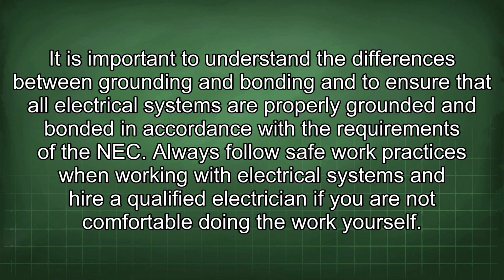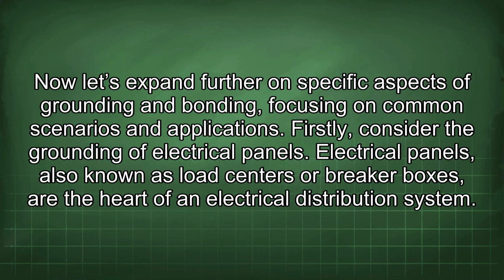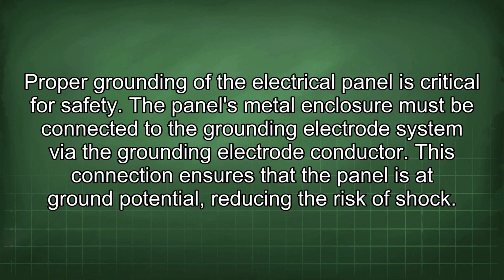Now let's expand further on specific aspects of grounding and bonding, focusing on common scenarios and applications. Firstly, consider the grounding of electrical panels. Electrical panels, also known as load centers or breaker boxes, are the heart of an electrical distribution system. Proper grounding of the electrical panel is critical for safety. The panel's metal enclosure must be connected to the grounding electrode system via the grounding electrode conductor. This connection ensures that the panel is at ground potential, reducing the risk of shock.